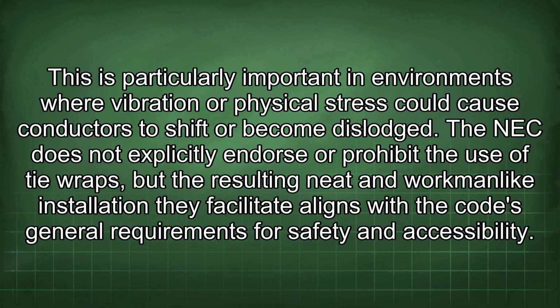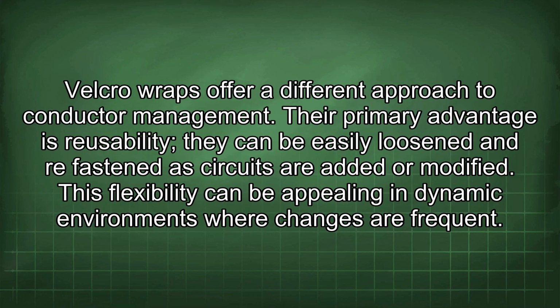This is particularly important in environments where vibration or physical stress could cause conductors to shift or become dislodged. The NEC does not explicitly endorse or prohibit the use of tie wraps, but the resulting neat and workmanlike installation they facilitate aligns with the code's general requirements for safety and accessibility. Velcro wraps offer a different approach to conductor management. Their primary advantage is reusability. They can be easily loosened and refastened as circuits are added or modified. This flexibility can be appealing in dynamic environments where changes are frequent.